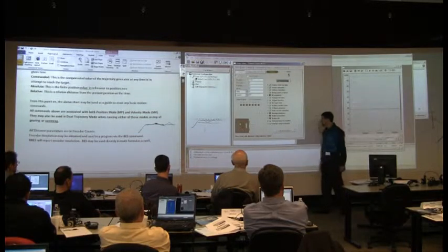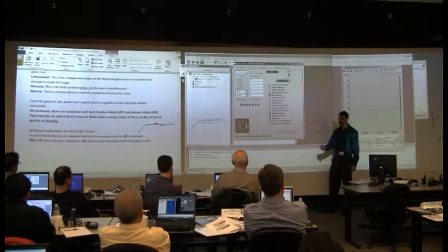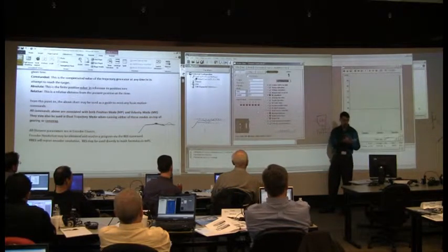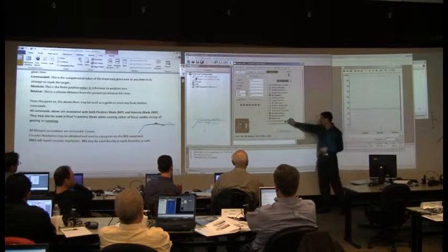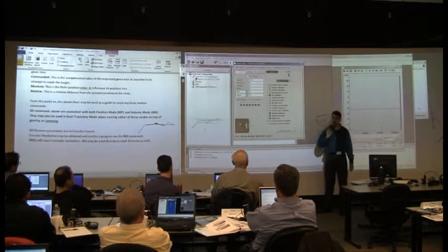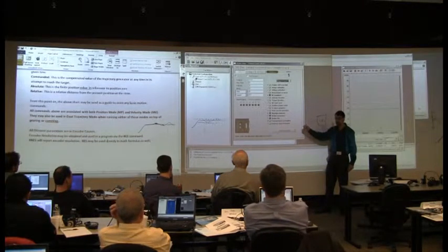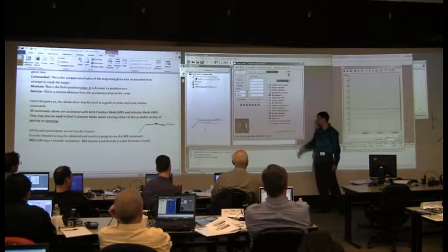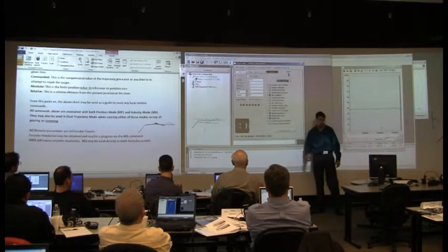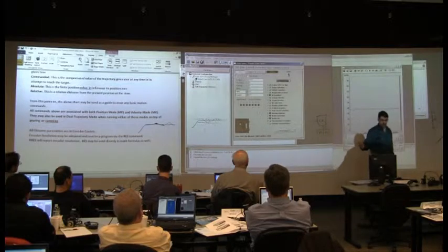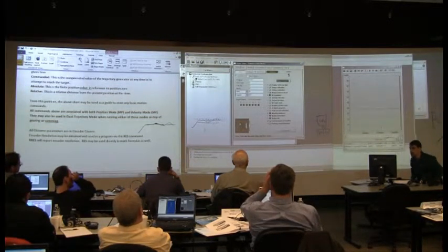External input go enabled. What the heck is that? That's a hardware feature that says, I want to make one of these inputs appear like the go command. When you enable that function, that means one of those inputs, if you give it a signal, it's the same thing as giving a go command at the terminal screen or inside the program. So that is a hardware feature. Velocity target reached, that's not really a hardware feature, that's a firmware deal. That just tells you you reached the velocity that you want to go to. If you command a certain velocity, it tells you when you reach it.